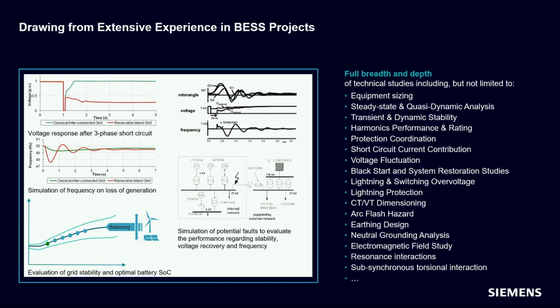Besides the standard steady-state, dynamic, and harmonic analysis to design or to verify the design and parameters of the components, we also conduct further studies, such as protection coordination to identify the correct protection device settings, voltage fluctuation to analyze the voltage dips in the system caused by energization of the plant components, short-circuit analysis to assess the impact of the BESS inverters on short-circuit currents within the system.